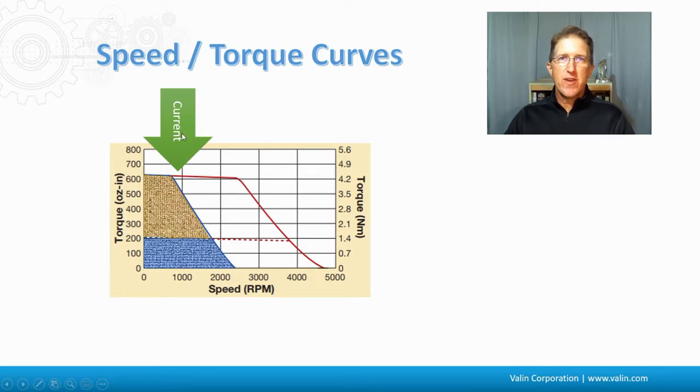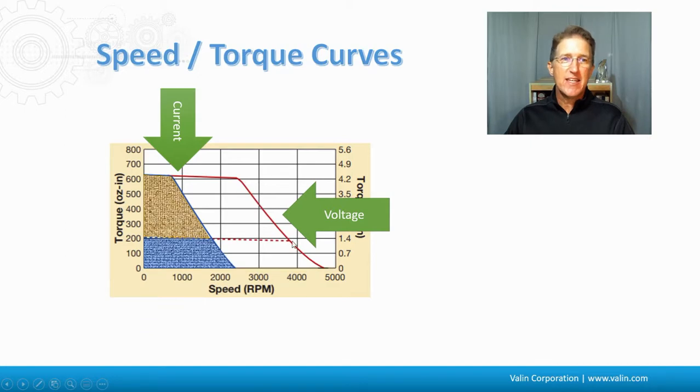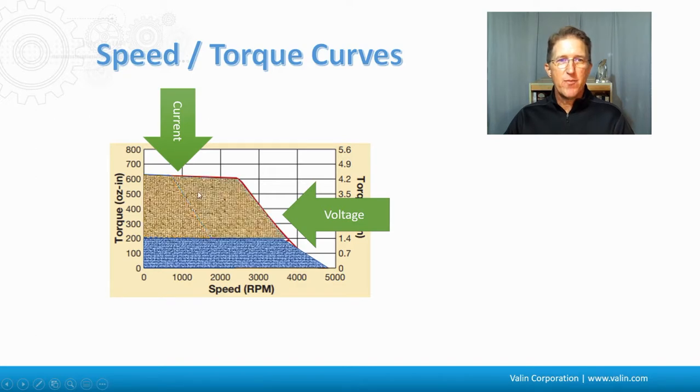The current that is available affects how much torque capability we have here, how much current the drive can put out, and how much bus voltage the drive has. That's the voltage potential that is inside the drive in the PWM switching frequency. Go back to a previous episode to understand that. That bus voltage capability is what defines this here. And again, at this higher voltage, we get more continuous and more peak there.